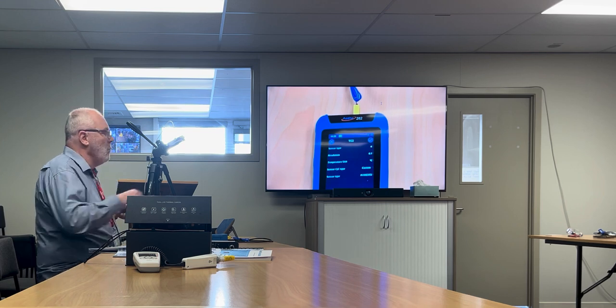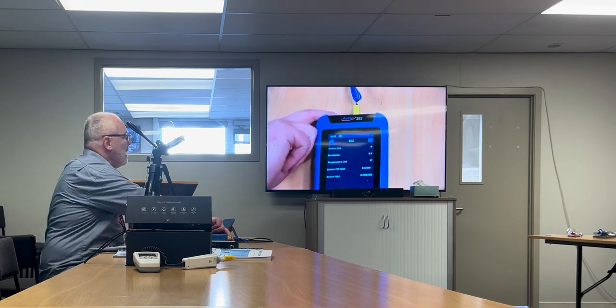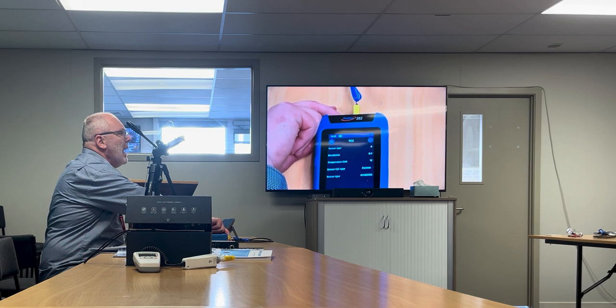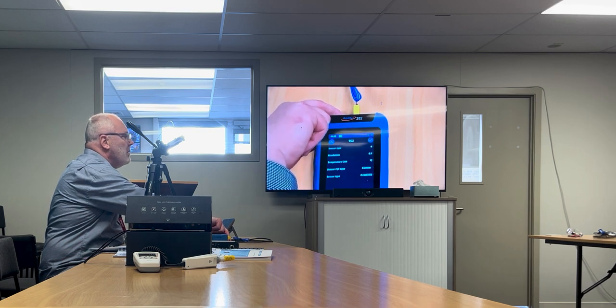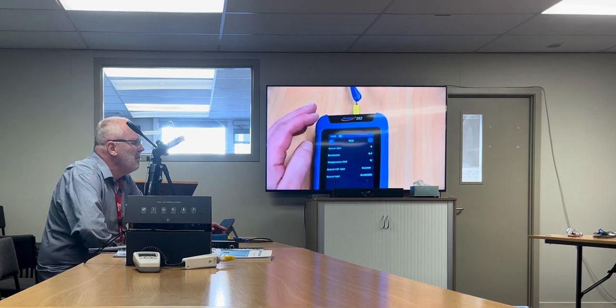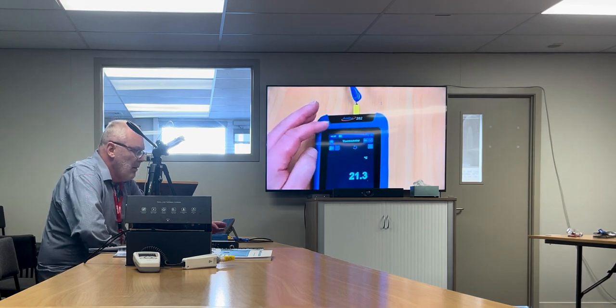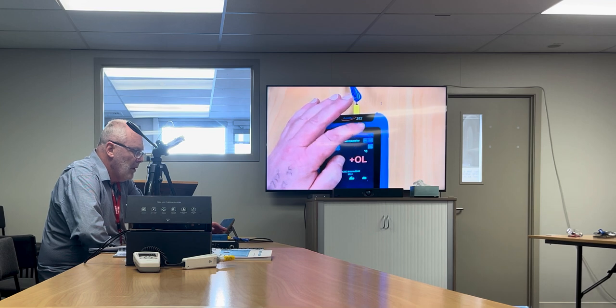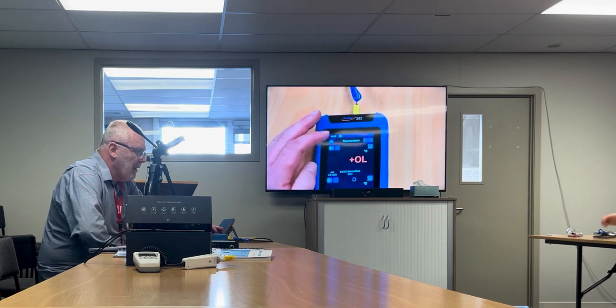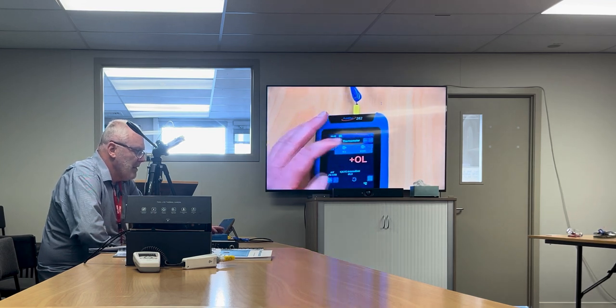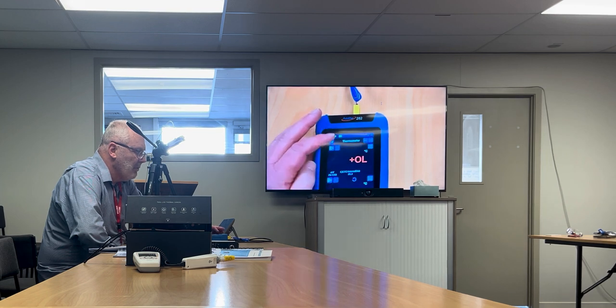So yeah, you could, if you wanted to, put a calibrated probe in channel one and use that as your cold junction reference. Pretty cool, pretty awesome. I don't think you'd have to do it often, no, but you might - probably just for the boilers we'd have to. Because normally you're looking at a resolution that isn't necessarily that hot. Thermocouples, as you know, aren't normally super accurate at the best of times.